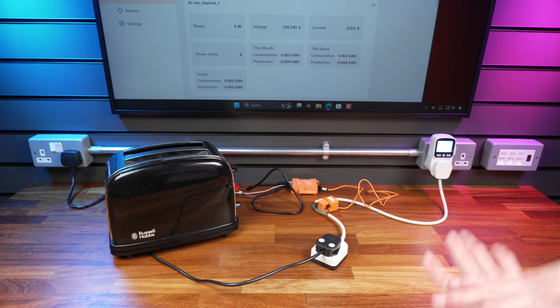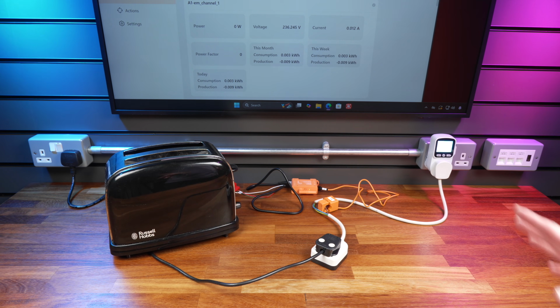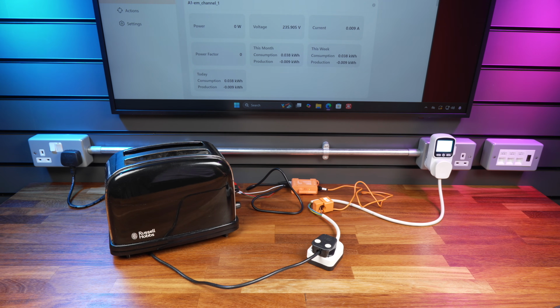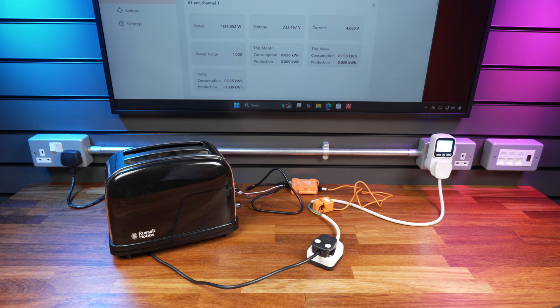This is a heating element, it's not got anything in it, no motors, nothing like that, so it should be purely resistive, meaning that the current times the voltage will be the amount of power in watts, and it should have a power factor of 1. So now, let's test this out. If we turn the toaster on, we can then refresh this page here. We're getting a reading of around about 1134 watts. Down here we're getting 1133 watts, so yeah, pretty close.